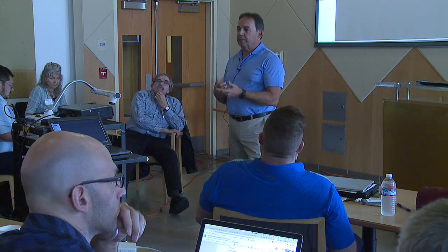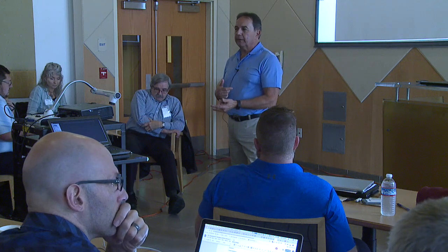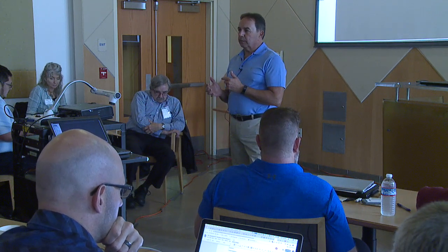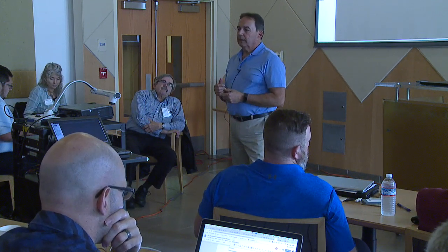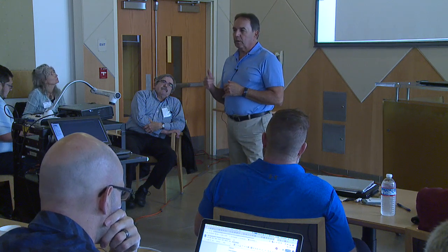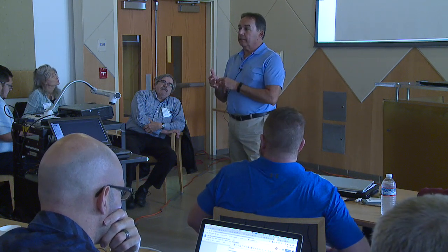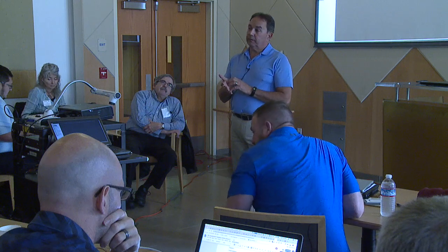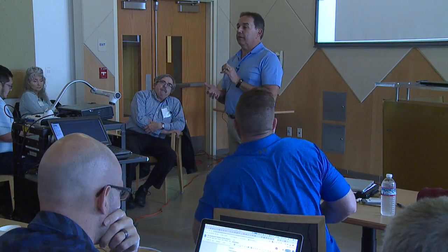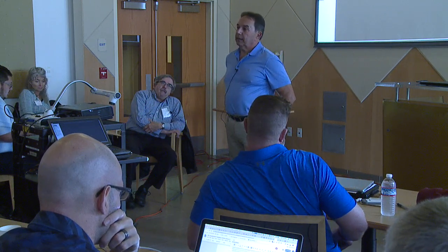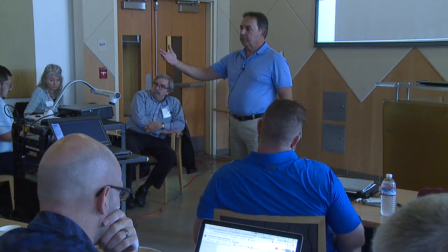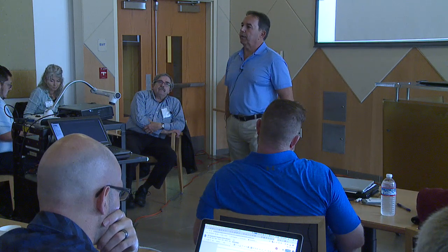Our sewer lift station emails and texts me if a pump fails. If the water in the boilers gets too cold, it'll text me. But the best thing is I can call any of my guys and they can log in remotely, even on their smartphone, and look at the system live to make corrections and changes. A lot of times there's an event on campus in the evening when we're all gone, and somebody needs a temperature adjustment - log in, change it, done. You don't have to get in a car and drive down to campus to do it.